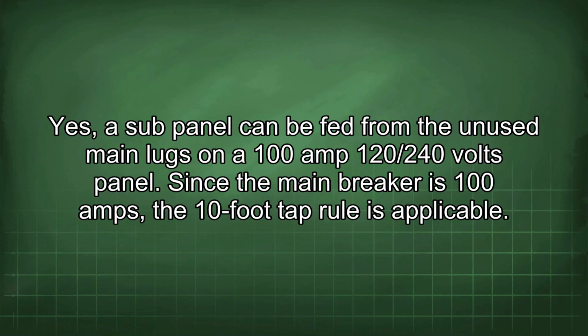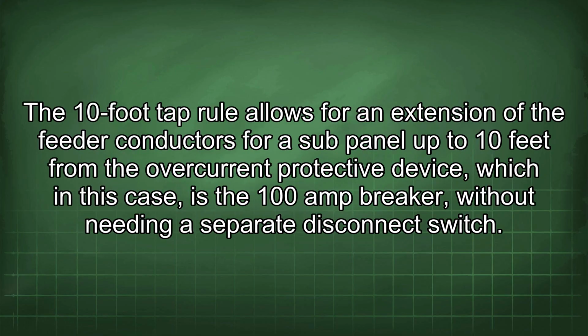Yes, a sub-panel can be fed from the unused main lugs on a 100 amp 120/240 volts panel. Since the main breaker is 100 amps, the 10-foot tap rule is applicable. The 10-foot tap rule allows for an extension of the feeder conductors for a sub-panel up to 10 feet from the overcurrent protective device, which in this case is a 100 amp breaker, without needing a separate disconnect switch.